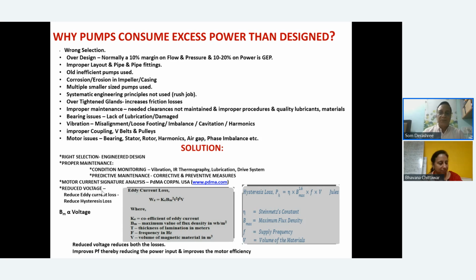Normally we find that there are always over voltages prevailing in the plant. Now by reducing voltage, what happens in motors? Actually, it's basically an induction machine, and there are copper losses and core losses. So the I square R loss is one part of it, depending on the load, you have to take care of that. But the no load losses in the motor, the eddy current and hysteresis losses, if you see in the formula, are in proportion to Bmax square. The flux density is actually proportional to the voltage. So as you reduce voltage, the maximum flux density Bmax also reduces, and your eddy current losses, which go as the square, and your hysteresis losses, which go as B to the power 1.6, also reduce substantially, thereby giving you some amount of savings.